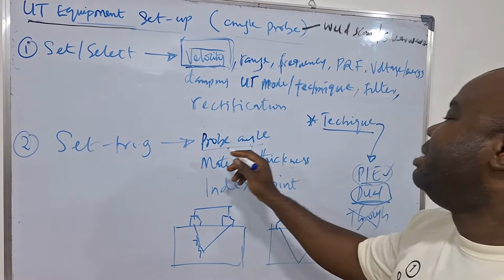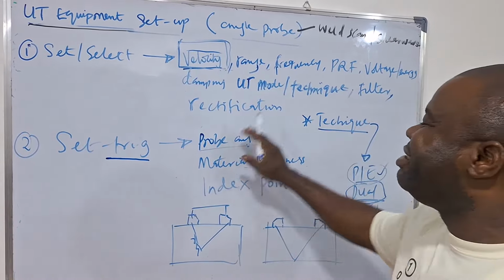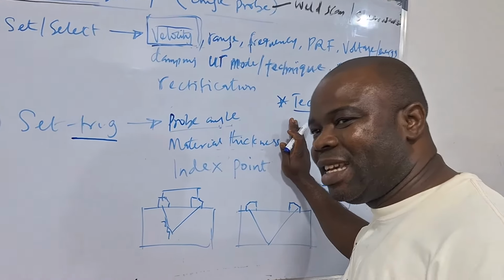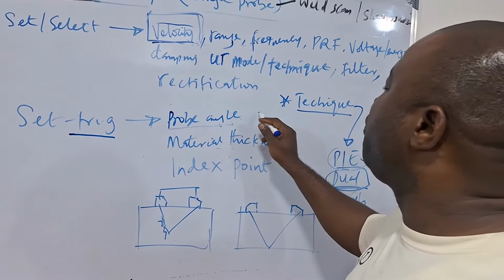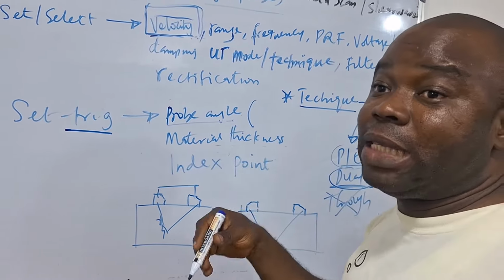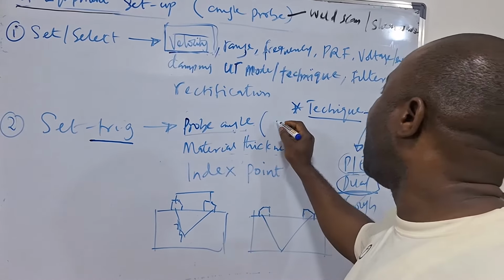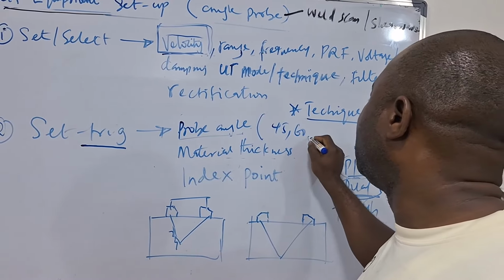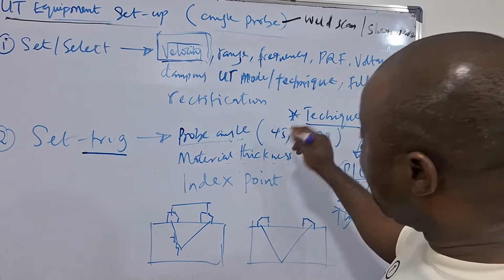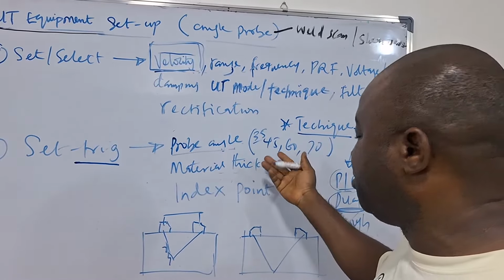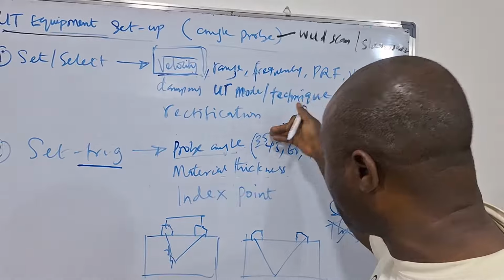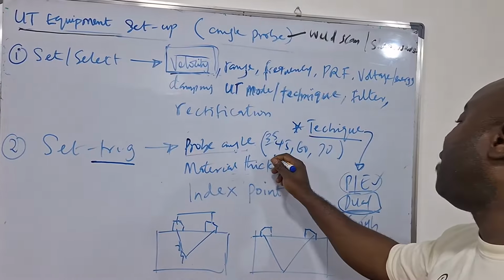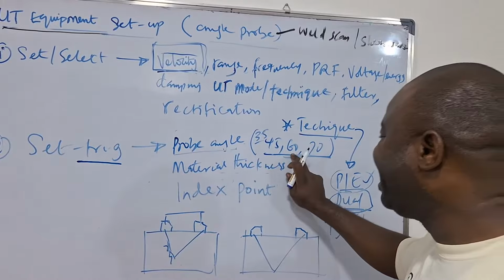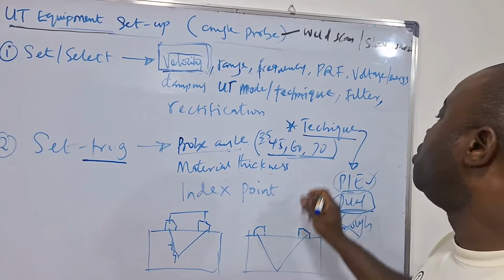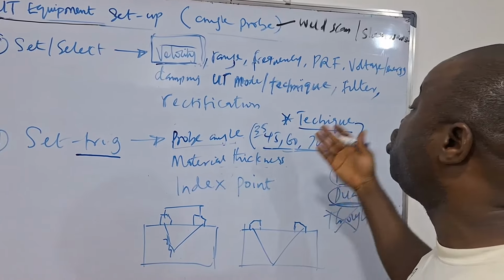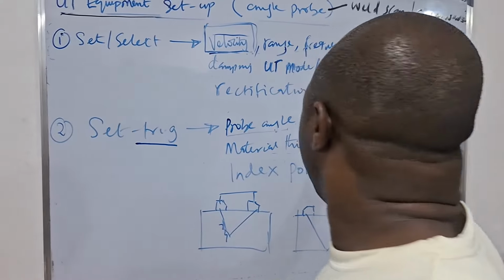Now, when you come to your trig, this is very, very, very critical. Because when you are doing your shear wave, you have a possibility of angles. Instead of your normal 0 degree that is just one angle, you have your 45 degree, you have your 60 degree, and you have your 70 degree. You have some other newer units that give you the option of 35 degree, like your Sonatest D50 gives you this option for 35 degree. But your commonly available probes are 45, 60, and 70 degree. You need to choose the right angle, because if you don't choose the right angle, you are going to be getting wrong results.